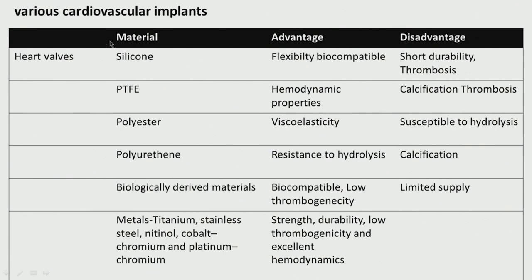Various cardiovascular implants — heart valves — use silicone, PTFE, polyester, polyurethane or biologically derived materials. PTFE has good hemodynamic properties, polyester is viscoelastic, polyurethane has resistance to hydrolysis, but they could have calcification or thrombosis. Biologically derived material is very good, but supplies are limited. For metals in heart valves: titanium, stainless steel, nitinol are all used.